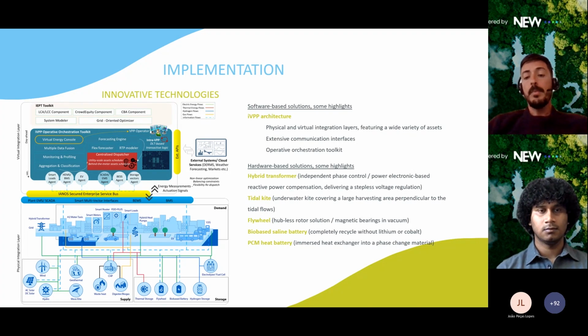The main highlights go to the hybrid transformer, the flywheel, and the phase change material heat batteries that will be deployed in Terceira. The hybrid transformer is an independent phase control transformer that is able to, through power electronics, compensate reactive power and deliver stepless voltage regulation.